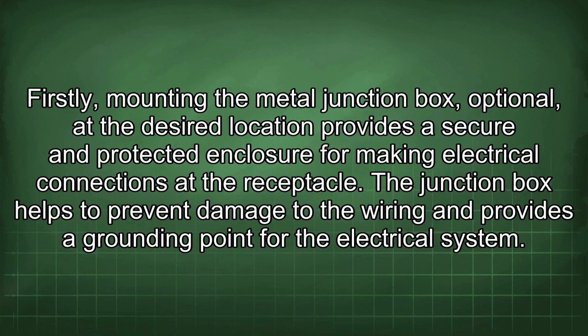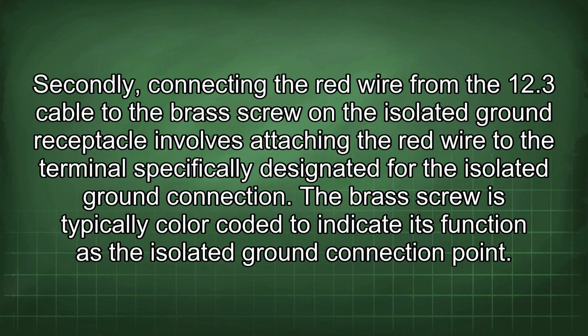Secondly, connecting the red wire from the 12-3 cable to the brass screw on the isolated ground receptacle involves attaching the red wire to the terminal specifically designated for the isolated ground connection. The brass screw is typically color-coded to indicate its function as the isolated ground connection point.